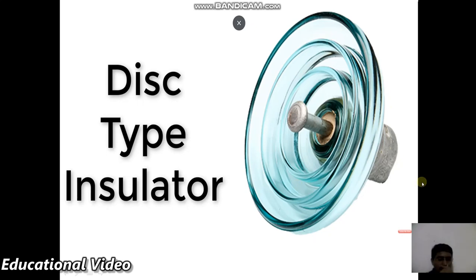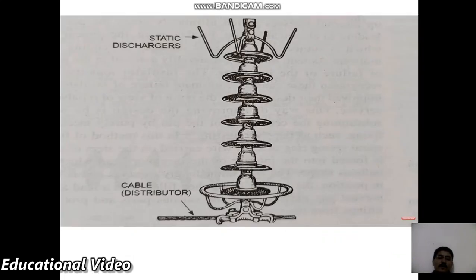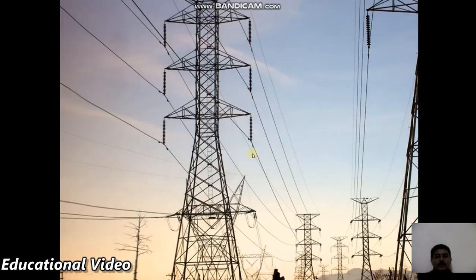Moving to disc type insulators, each disc provides insulation for approximately 11 kV. Depending on the voltage level required, the number of discs is increased. When multiple discs are connected together, they form a string. This is visible in the picture of a transmission tower where such a disc string can be observed.